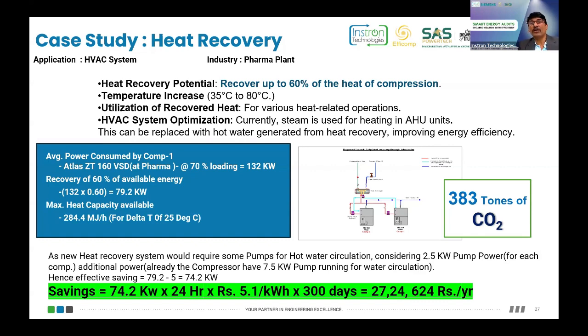With this compressor, we were able to fulfill their overall plant demand, and the steam which was being used earlier for heating water was replaced, or rather actively extracted from the compressor. We were able to reduce around 383 tons of carbon dioxide emission, which in terms of rupees is a big value, around 27 lakh rupees, just by recovering heat from the system.